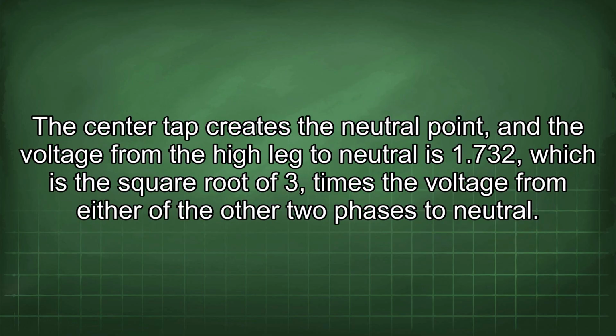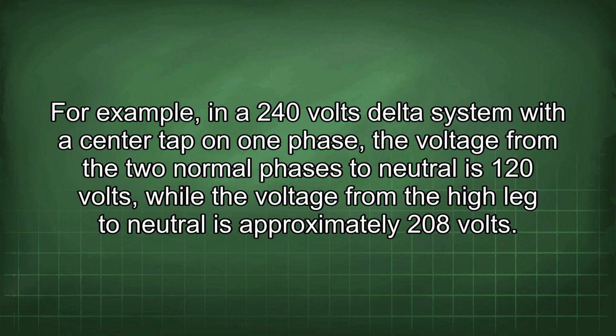The center tap creates the neutral point, and the voltage from the high leg to neutral is 1.732, which is the square root of 3, times the voltage from either of the other two phases to neutral. For example, in a 240 volt delta system with a center tap on one phase, the voltage from the two normal phases to neutral is 120 volts, while the voltage from the high leg to neutral is approximately 208 volts.